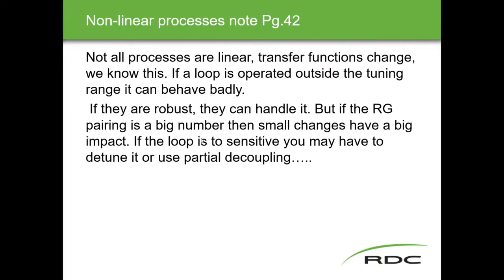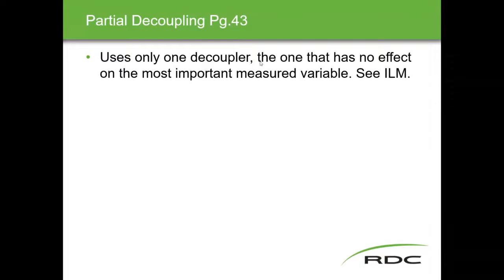If the loop is too sensitive, you have to go back to detuning strategies or use partial decoupling. Partial decoupling uses only one decoupler — the one that has no effect on the most important measured variable. For example, in a loop with a composition transmitter and a flow transmitter, composition is probably more important, so you use the decoupler that doesn't affect composition. That's almost like turning it into a ratio control situation.